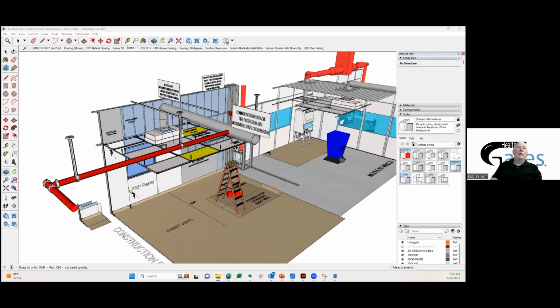The next level is USP ISO 7, which is 10,000 particles, so you can see that's quite a jump. That is in all of the sterile buffer rooms, and their purpose is to protect the hood, which is ISO 5, less than 100 particles. But they've also added a velocity requirement that the air has to be uniform. So that's really the ideal sterile setup.